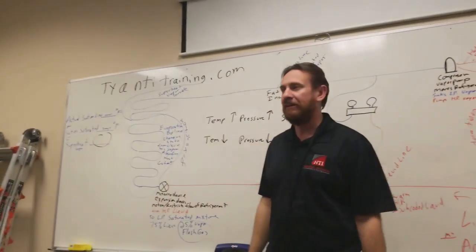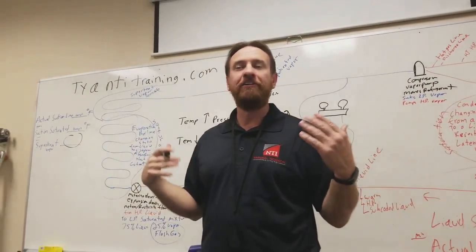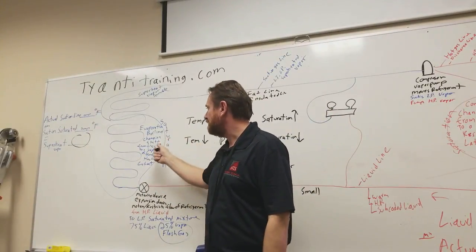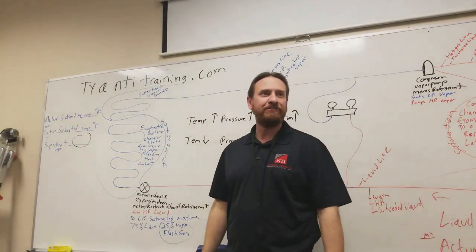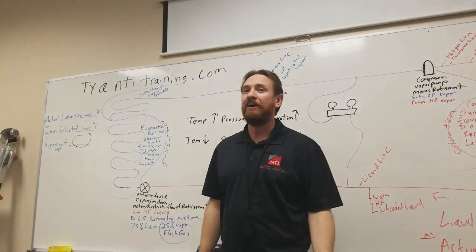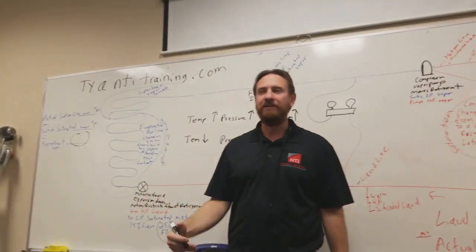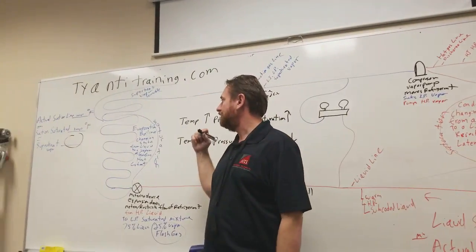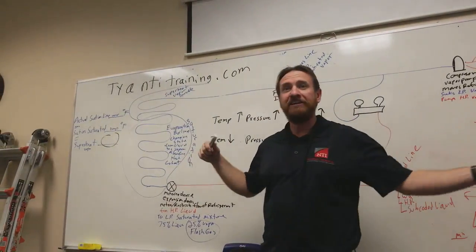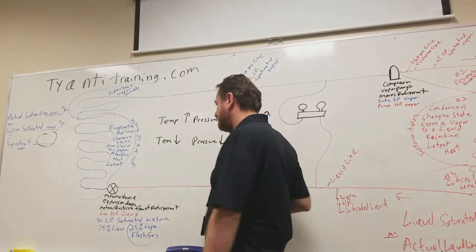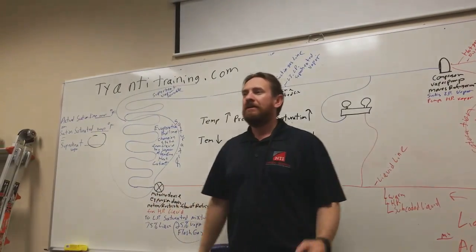We're going to come back to this later, but at least it gives you a starting point of why it freezes. Saturated temperature below 32. Done. That's the answer to the question. Now, things that cause that: the number 1 reason, airflow. Number 2 reason, low refrigerant. Number 3 reason is temperature too low, outside or inside. And the last reason is some kind of mechanical restriction.